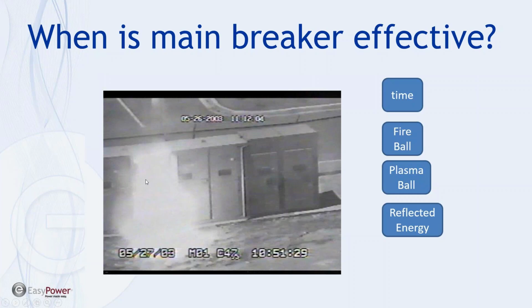It's worthy of note that there's an area here at the top of the cabinet which extends beyond the circular area. This is actually reflected energy from the back of the cabinet because this is a closed box, and it's amplifying the energy that these people are being exposed to, especially the people that are standing up. Now, because this is an arcing event, at the heart of this fireball is a plasma ball. And just by the general physics of the way this works, I think the estimates were this was between an 8 to a 12 calorie explosion, that the plasma ball more than likely is somewhere between 3 and 6 inches in diameter, and that's what's producing this amount of energy release.